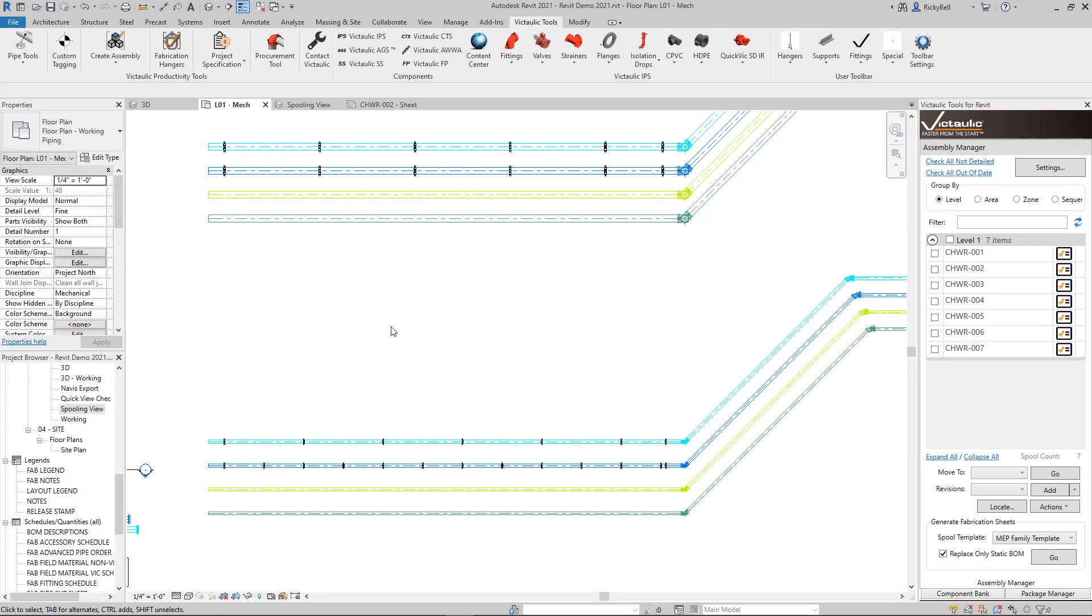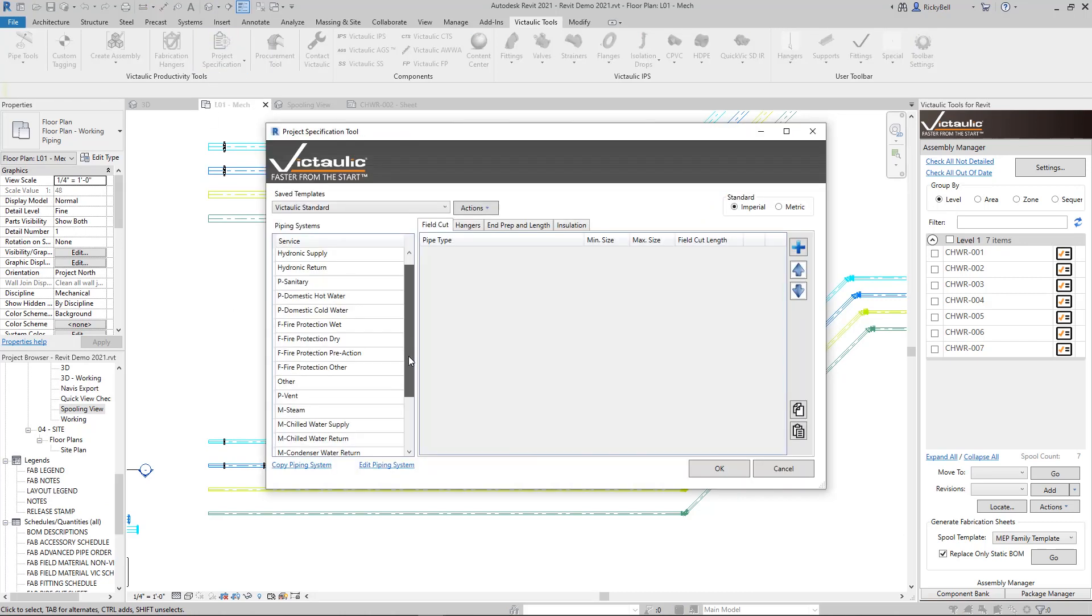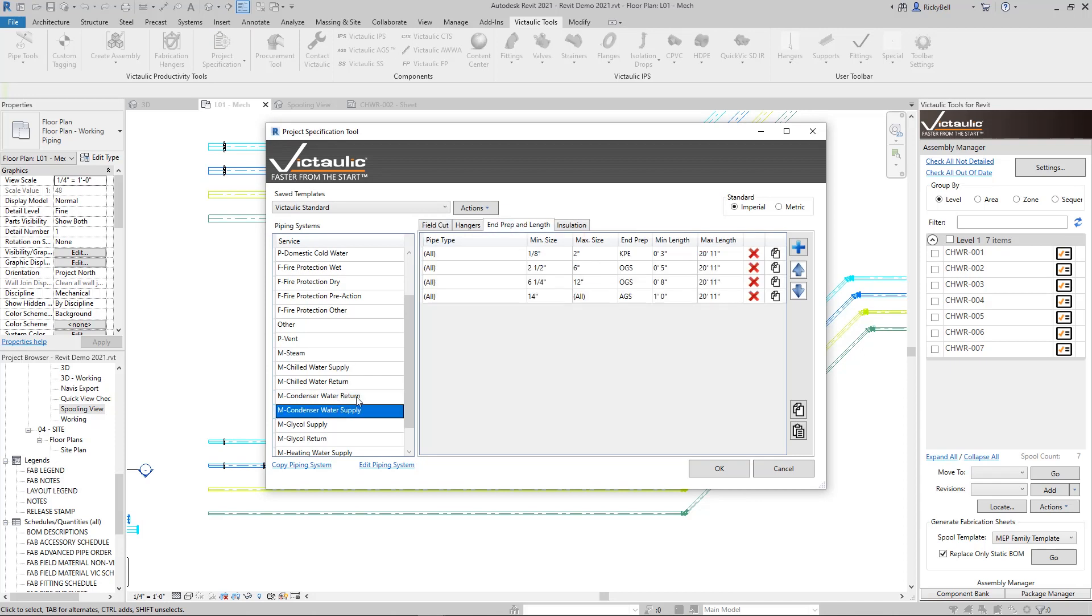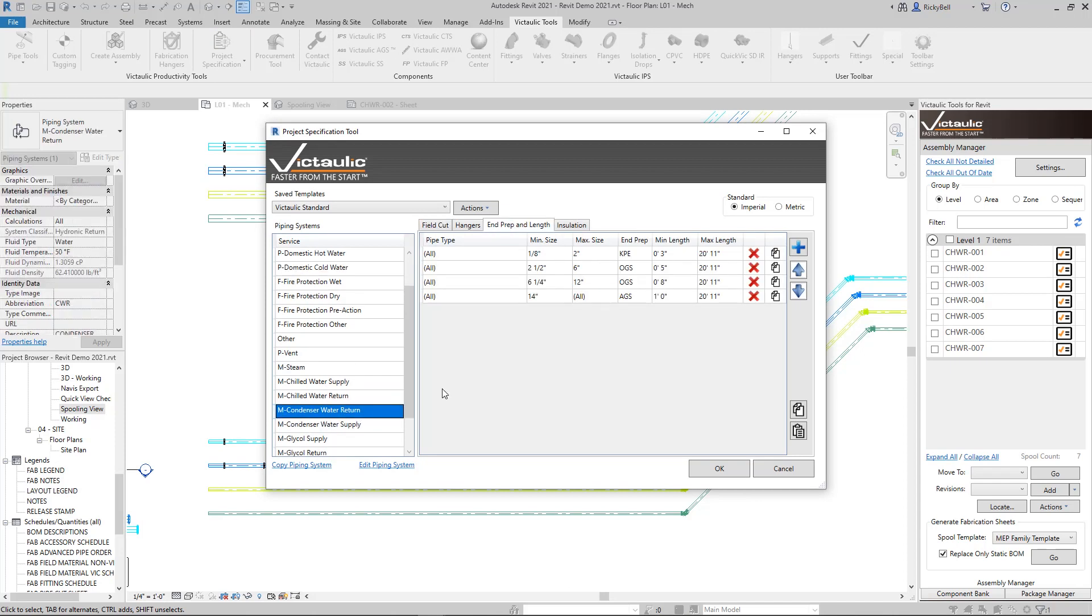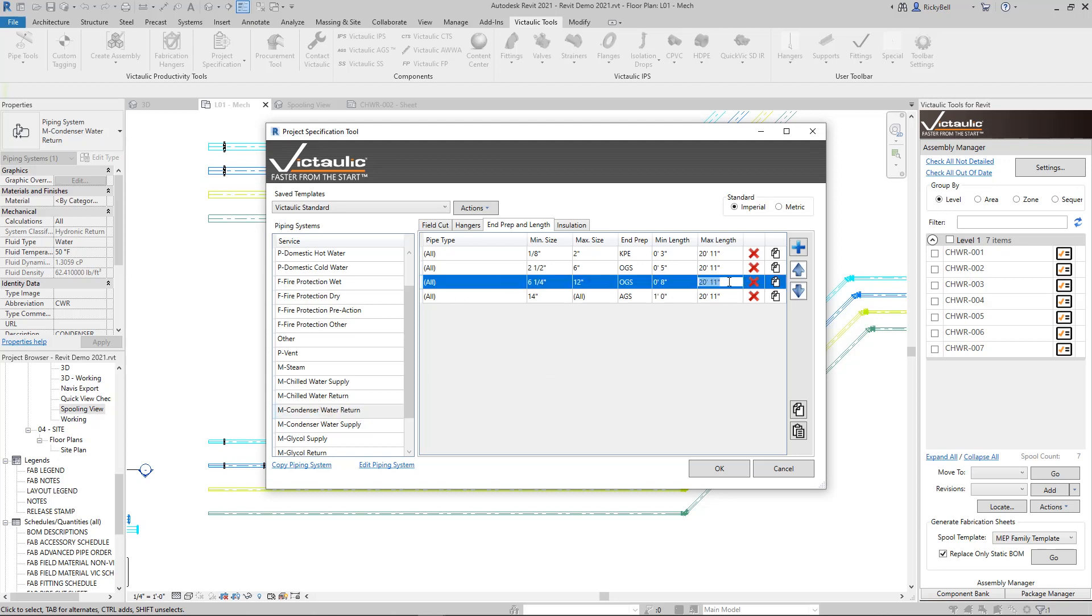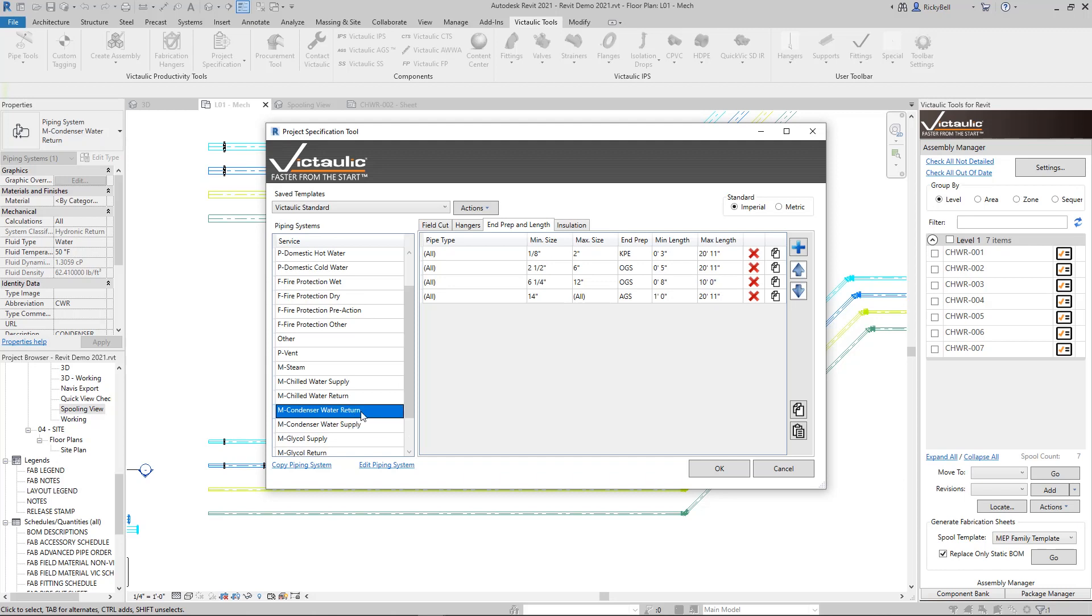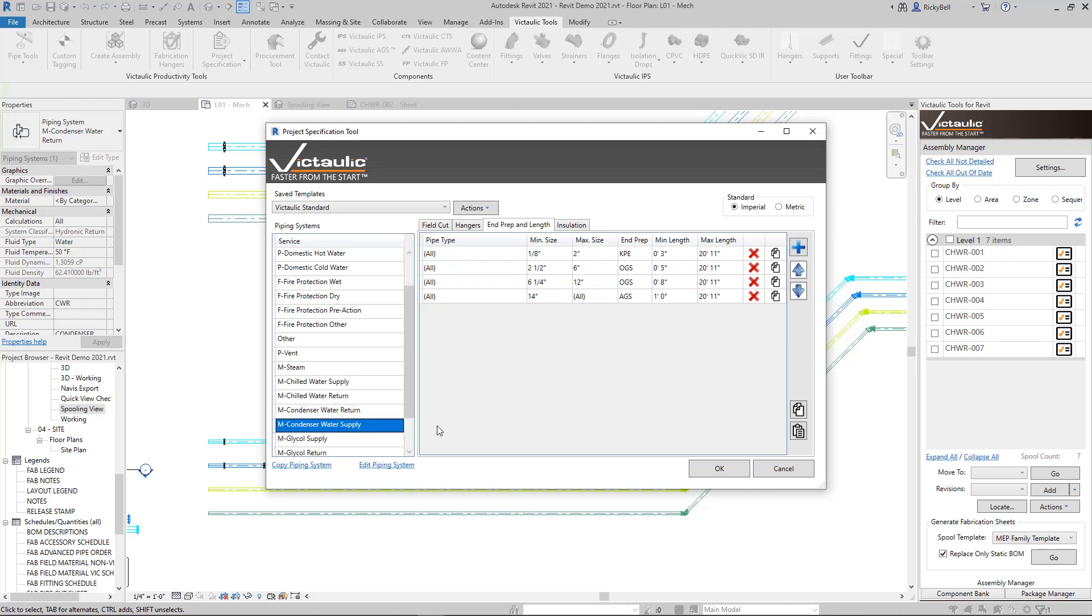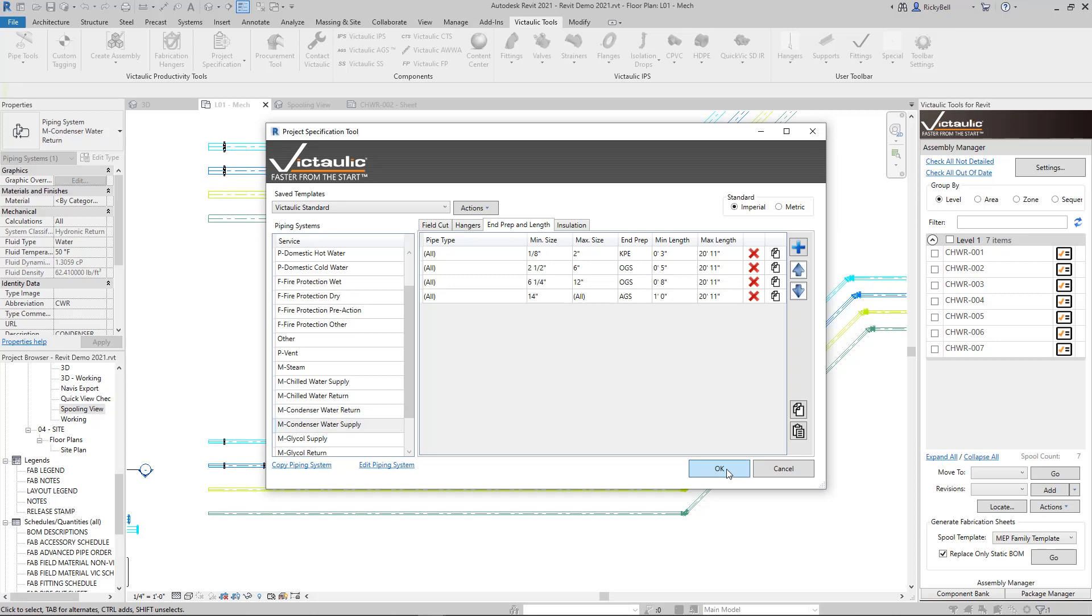Even some of the familiar tools in our toolbar like pipe splitting can be driven from the project spec tool as well. These other two systems I have down here are condenser water return and condenser water supply. Let's set some different rules for our return as we do our supply. If you remember we have 10 inch pipe and 4 inch pipe. So let's say our return line for 10 inch needs to be split at 10 feet. Our supply line for 10 inch will still get split at 20 foot 11. And then maybe even our smaller sizes, let's say we'll split these at 8 feet for return, and we'll leave it at 20 foot 11 for supply.